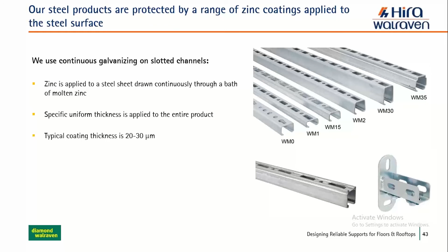On corrosion protection, since we're talking about exposed installations, our steel products are protected by a range of zinc coatings. Depending on site or installation conditions and requirements, we select the appropriate zinc coating to apply to the steel. For slotted channels, by standard we apply continuous galvanizing, where zinc is applied to a steel sheet drawn continuously through a bath of molten zinc. This allows a specific uniform thickness, typically about 20 to 30 microns.